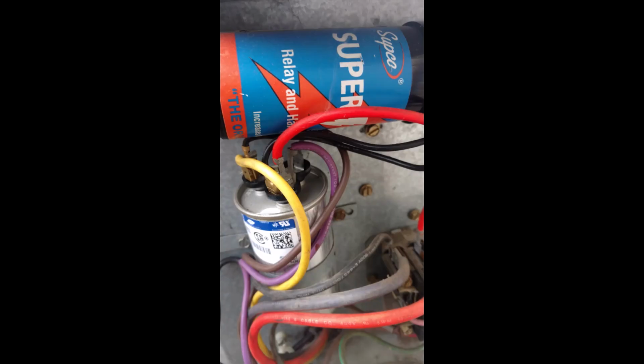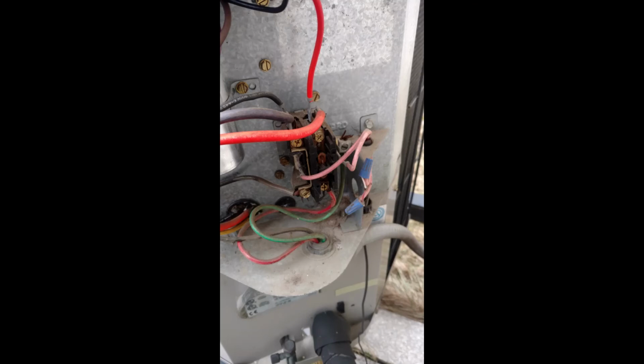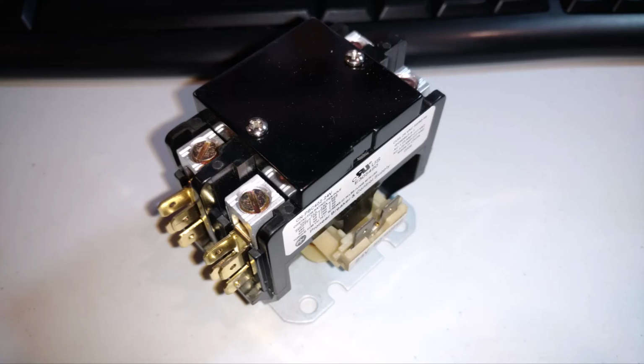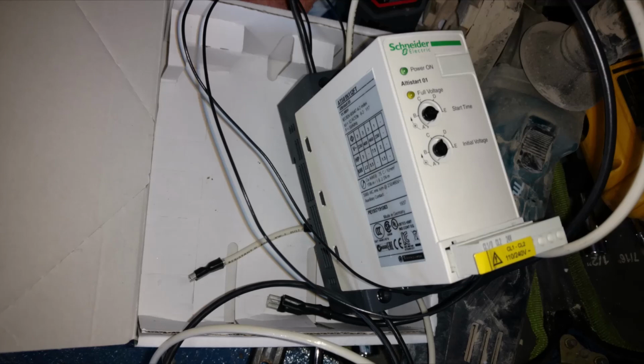When this is done, the large multi-tap capacitor fan connection will go unused because the ECM motor doesn't need a run capacitor. My outdoor condenser has a contactor, but only one leg of the 240 volts is interrupted, so I'll be installing a proper 2-pole relay to interrupt all the power in the outdoor unit. So that takes care of 2 of the 3 main motors in a central air conditioner. That leaves the refrigerant compressor.